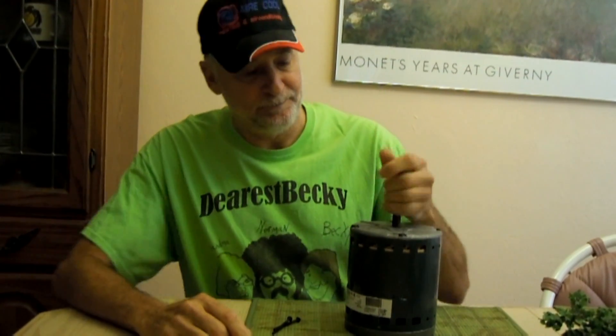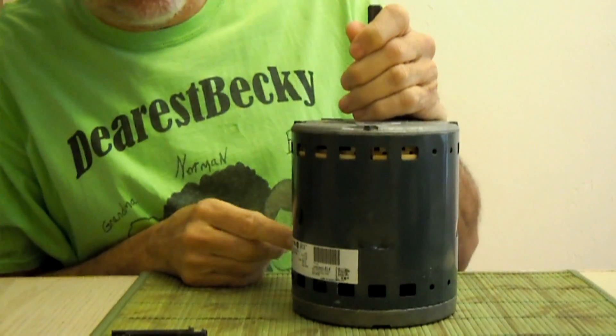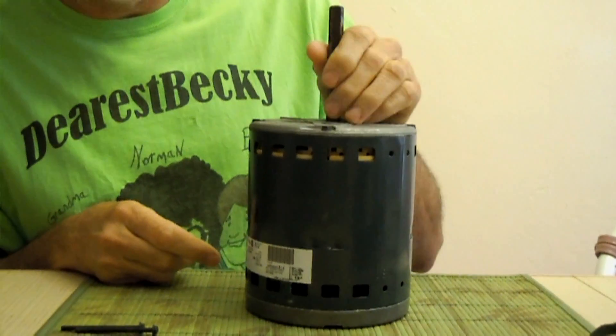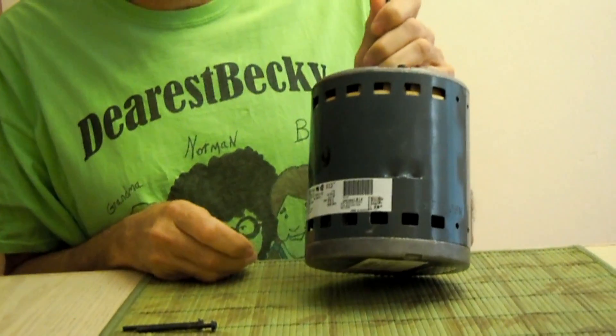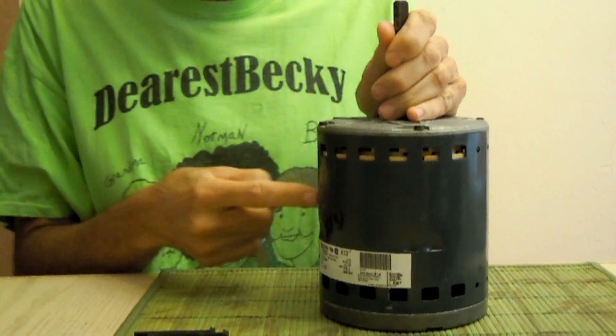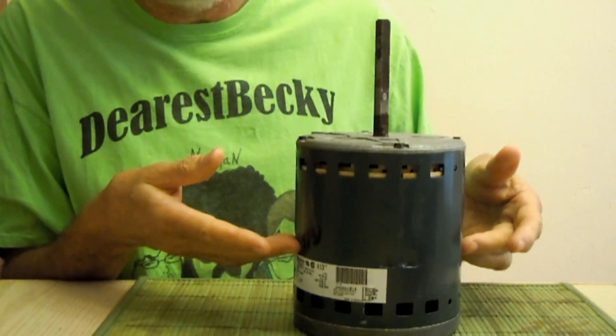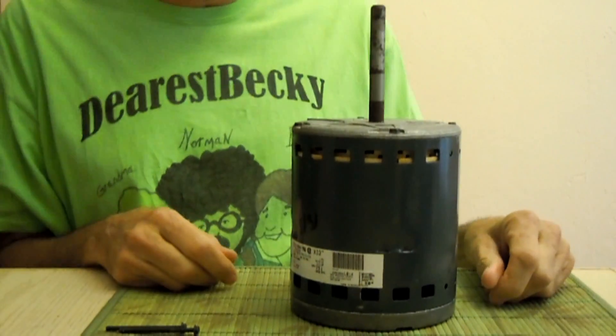Anyway, here's what this video is about — it's about ECM motors. What I have here is a GE ECM motor. I took this out of the dead motor bin over at Baker Distributing. I was really interested in looking at it because there were so darn many of this particular motor in that bin. It turns out these motors go in Nordyne air conditioning systems — this is a three-quarter horsepower blower motor, half-inch shaft, 48Y frame.